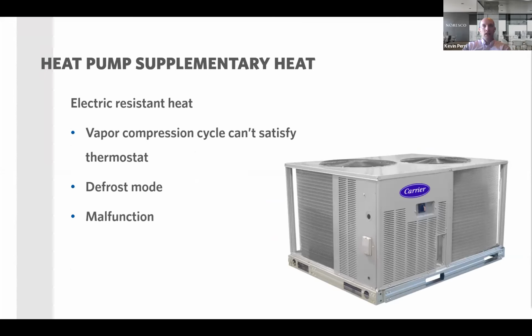So another new update in the 2021 code cycle has to do with supplementary heat on heat pump systems. What they've said is that when your heat pump has the ability to provide supplementary heat, it can only happen when one of the following is happening. So the vapor compression cycle basically can't satisfy the thermostat, can't keep up with the space temperature. Then you can use your supplementary heat.